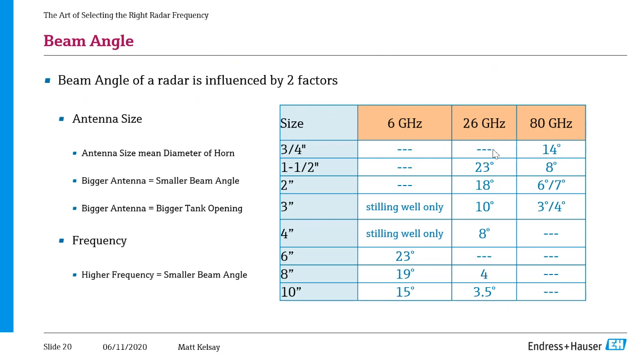So the first is your antenna size. And when I say antenna size, what I mean is the diameter of that horn. So the bigger your antenna, the smaller your beam angle is going to be. However, with a bigger antenna, that means you've got to have a bigger opening in your tank. So if you've got a 4-inch antenna, typically you need a 4-inch nozzle in your tank to be able to install it. So if you look at the chart, let's just focus on that middle column of 26 gigahertz.